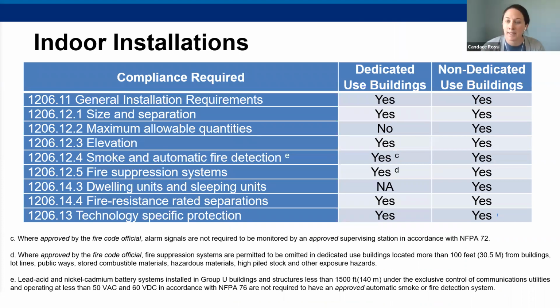So this is a list of the compliance that indoor installations need to meet. We have already reviewed the general installation requirements, the electrochemical protections, the chemistry specific protections. And here you can see the different requirements that indoor installations might be required to meet, depending on their use. So for dedicated use buildings, they must meet the general installation requirements, the size and separation, but they are not required to meet that maximum allowable quantity. So they can go over that 600 kilowatt hour for lithium ion without doing a large scale fire testing, though it is very, very extremely likely that they'll still have to do that testing for other reasons. Just it won't be required due to that one requirement.